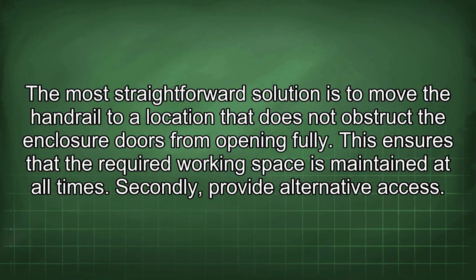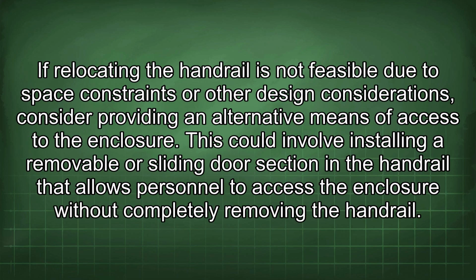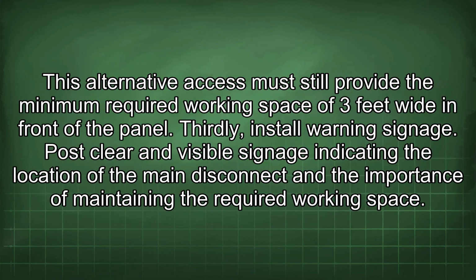Secondly, provide alternative access. If relocating the handrail is not feasible due to space constraints or other design considerations, consider providing an alternative means of access to the enclosure. This could involve installing a removable or sliding door section in the handrail that allows personnel to access the enclosure without completely removing the handrail. This alternative access must still provide the minimum required working space of 3 feet wide in front of the panel.